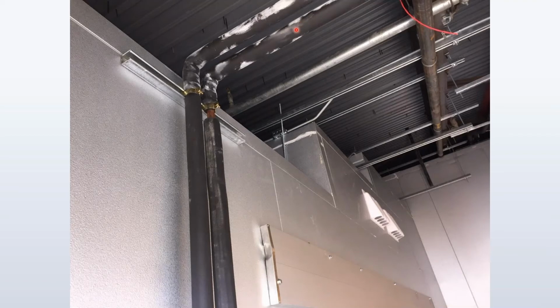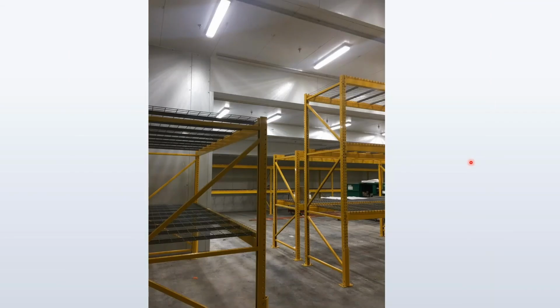From this angle, you can see the walk-in is one height for 12 to 15 feet. Then it steps up for a few feet and then over another 8 feet or so, up another couple, and then finally up to the main body of the walk-in. From the inside of this walk-in, you can see this stair stepping really maximizes capacity. The stepping here is referred to as a roof height transition.